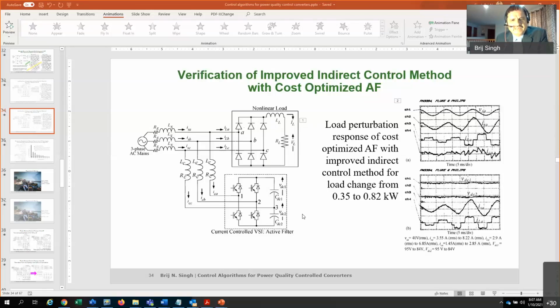So there are two methods to compensate. One is, of course, you use a shunt filter like I have here. Another one, you turn that drive rectifier into a controlled converter, like active rectification - you replace the converter with an active rectifier, also called a voltage source converter. That would be one application where you replace it, and then you handle all the harmonics because it's doing active rectification. The control switching elements shape the current to be sinusoidal. So that would be one application. We call them VSI, voltage source inverter - but essentially this is also called a VSI, working in rectification or active rectification mode. So that's one application of such a thing.